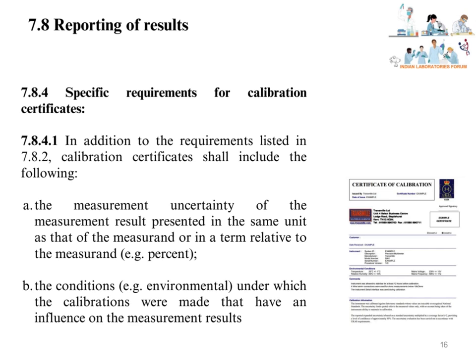Specific requirements for calibration certificates. In addition to the requirements listed in 7.8.2, calibration certificates shall include the following. The measurement uncertainty of the measurement result presented in the same unit as that of the measurand, or in a term relative to the measurand, for example percentage. That is, reporting of measurement uncertainty in the same units or relative terms of the measurand results. The conditions, for example environmental, under which the calibrations were made that have an influence on the measurement results. For example, temperature, humidity, etc.